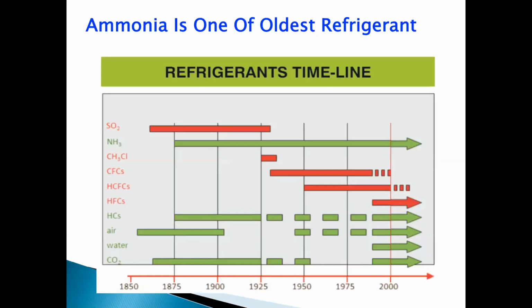As I was telling you, ammonia is one of the oldest and longest-running refrigerants. Why do we say ammonia? It's a natural refrigerant. It's been in industry for more than 125 years, almost 150 years, and it's still going on. Many refrigerants have come and gone. Ammonia has been there since 1875 and is continuing. CO2 was there before ammonia, then it was discontinued, and now we are again having plants with CO2 or CO2 ammonia systems. CFCs, HCFCs, many of them have come and gone, and are on their way out. Ammonia is the only one you can see going throughout the life cycle of these refrigerant plants.